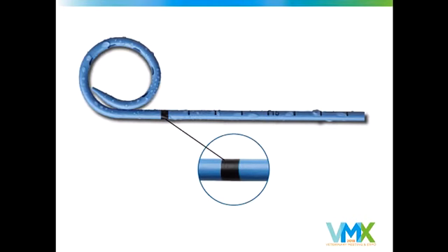Some of the locking loop catheters actually come with a really dramatic radio opaque marker, so you can see exactly where this is. Not all of them have this. The whole tube is always visible, but the extra black marker makes it even easier to see. If this is in your target zone, then you're 100% sure that your loop with the variable number of perforations is in your target body part.